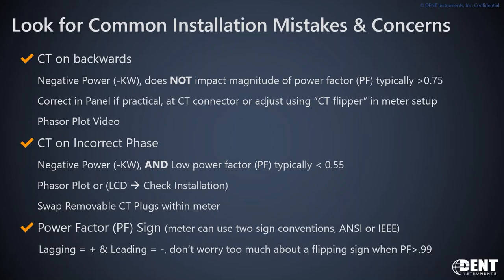If you can correct a backwards CT physically at the CT itself, that's best practice — so installers who come behind you don't inadvertently reverse it again. If you can't fix it at the CT, you can actually fix it at the meter end by swapping the color codes in the terminal. And if you've left the site, you can swap those electronically through the configuration tool itself.